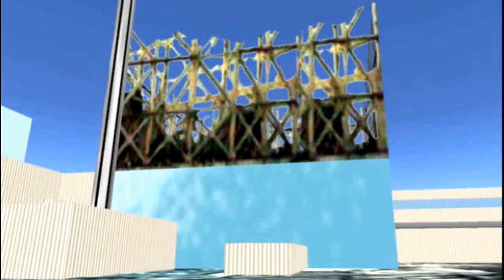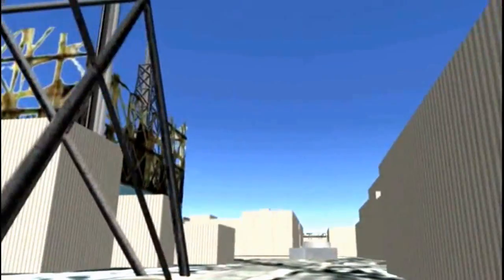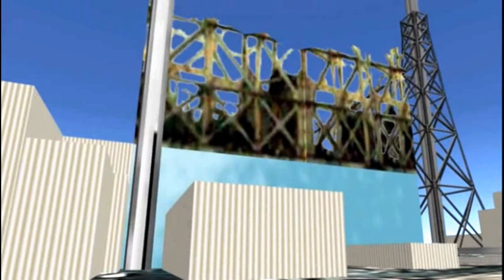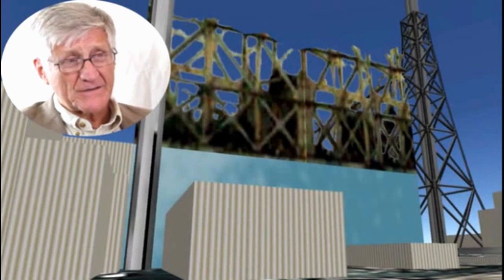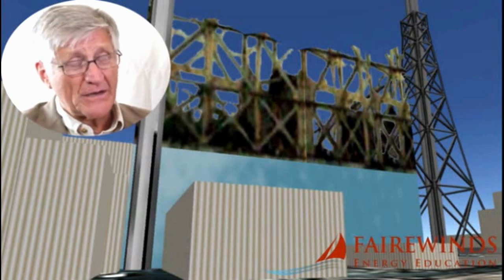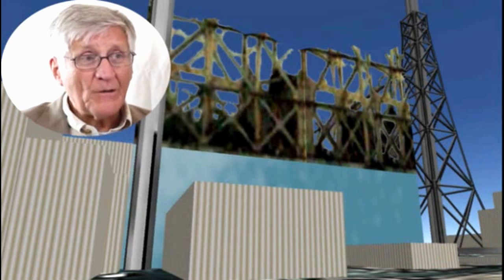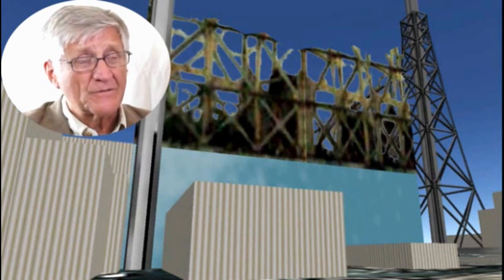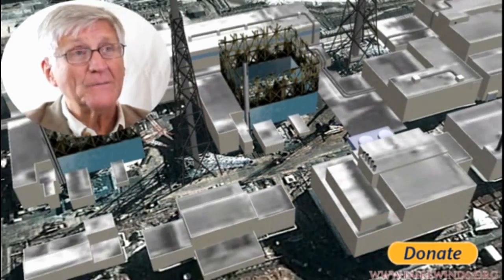Let's go down to Daiichi 4. Daiichi 4 wasn't running when the accident happened, but it exploded as well. What made it dangerous was that all of the nuclear fuel wasn't in the containment — it was all in the fuel pool. This was the biggest concern among experts after the accident and the reason Americans evacuated out to 50 miles. The fuel was physically hot, and if the fuel pool didn't get enough water, it would have drained and caused a meltdown inside the fuel pool with nothing between it and the sky.